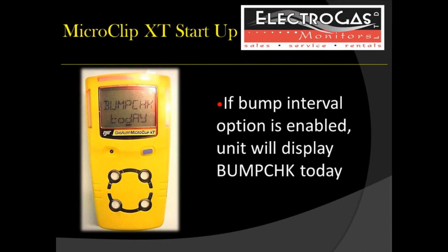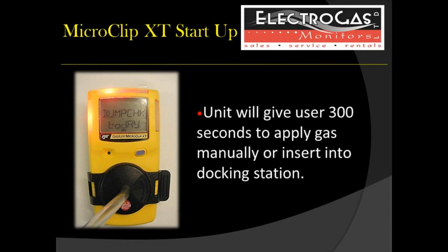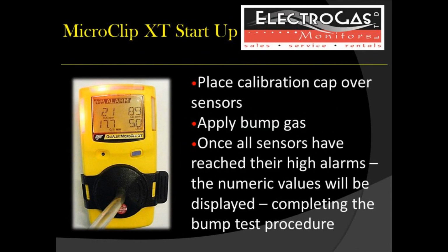If you have enabled the bump interval option on your MicroClipXT, the unit will display Bump Check Today. The unit will give you 300 seconds to manually apply gas or insert your monitor into a BW docking station. To perform a manual bump test of your monitor, place the calibration cap over the sensors and apply your 4-gas mixture. Once all the sensors have reached their high alarm set points, the numeric values will be displayed, completing the bump test procedure.